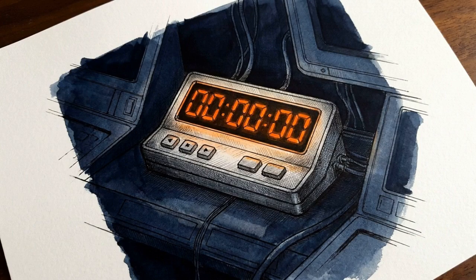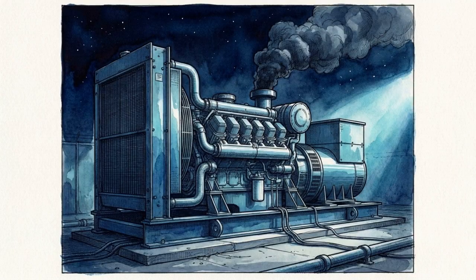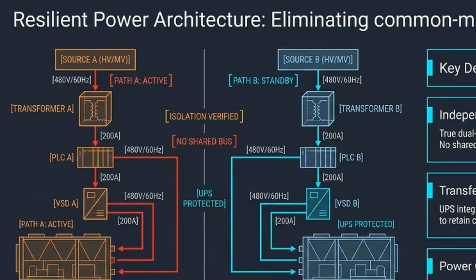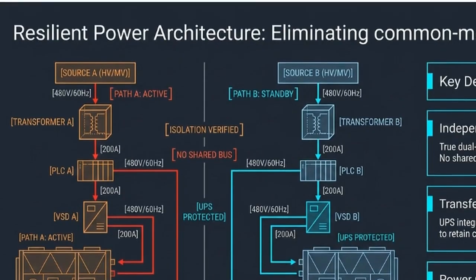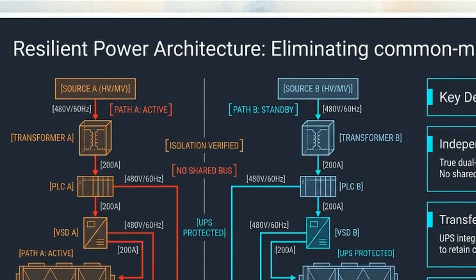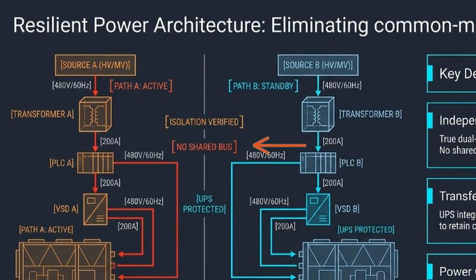Between 0 and 15 seconds, the facility detects the outage and the backup generator begins supplying a usable alternate power bus. Looking at the power architecture, we see the isolation required to survive. Source A, the utility grid, drops offline, but Source B remains ready. The generator engages, feeding path B. There is no shared bus, eliminating the risk of a crossover fault.